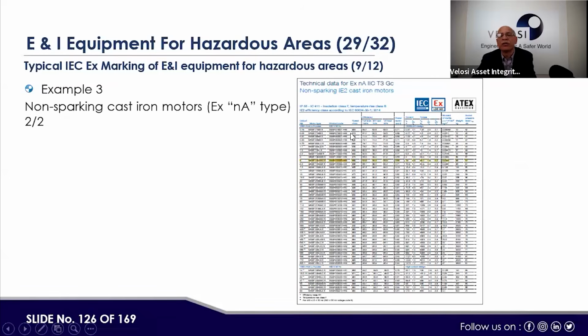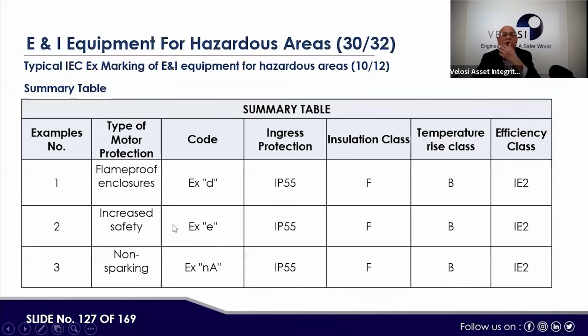If we make the summary of this, it is a further specification and the other data. Then if we try to make the comparison, the type of motor protection: first one is flame proof enclosure, increased safety, the non-sparking, the codes D, E, and NA are there. Ingress protection is IP-55 for all. Insulation class of the motor, which is applicable in the motor, is F, and temperature rise class is B, and efficiency class is IE2. And EPL would be separate basically for this. This is for the motor internal, like a safety.